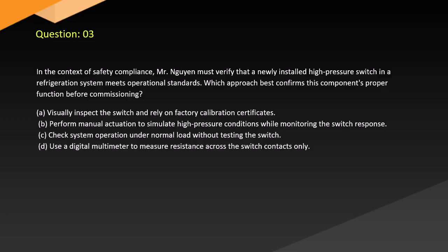Question 3. In the context of safety compliance, the technician must verify that a newly installed high-pressure switch in a refrigeration system meets operational standards. Which approach best confirms this component's proper function before commissioning? A. Visually inspect the switch and rely on factory calibration certificates. B. Perform manual actuation to simulate high-pressure conditions while monitoring the switch response. C. Check system operation under normal load without testing the switch. D. Use a digital multimeter to measure resistance across the switch contacts only.